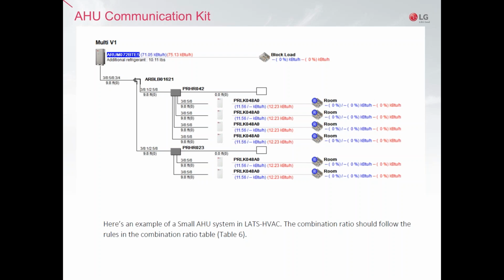When you have a configuration like this one, where you can have maybe six small different indoor units in a building, heat recovery is the way to go, because in this kind of configuration you can have some of the units working in cooling and some of the units working in heating. We also have another software called LATS CAD, which is very similar, but instead of using a drawing like the one you see here, you are actually working in a CAD drawing, pulling and putting the units in the system.